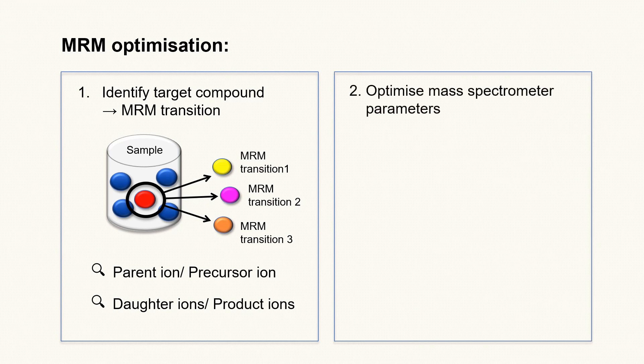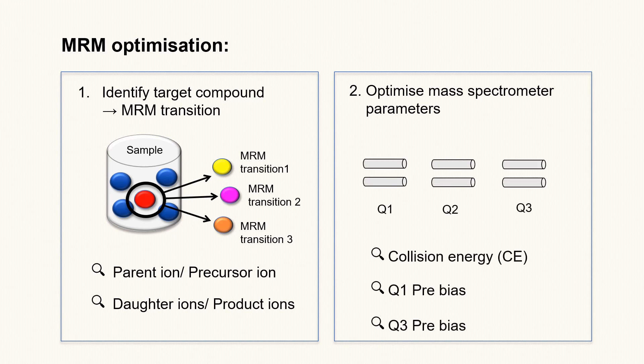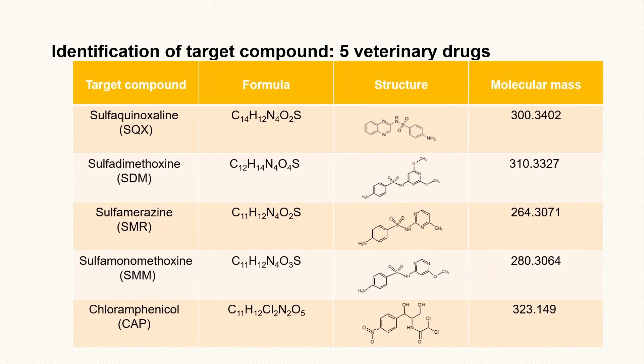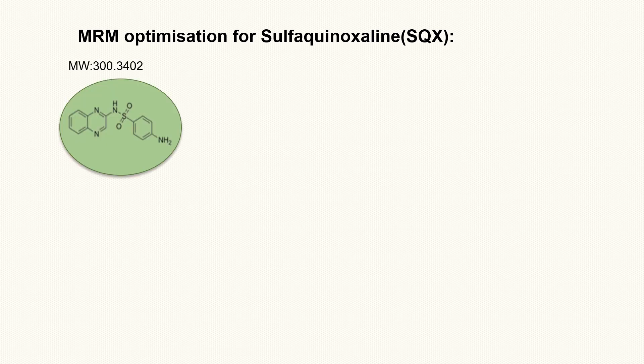Thereafter, mass spectrometer parameters such as collision energy, Q1 pre-bias, and Q3 pre-bias have to be optimized to achieve the best result. To begin setting up a method for detection of veterinary drugs in LC-MS-MS, basic information including formula, structure, and molecular mass are listed. The following diagram shows the MRM optimization process of the veterinary drug sulfaquinoxaline.